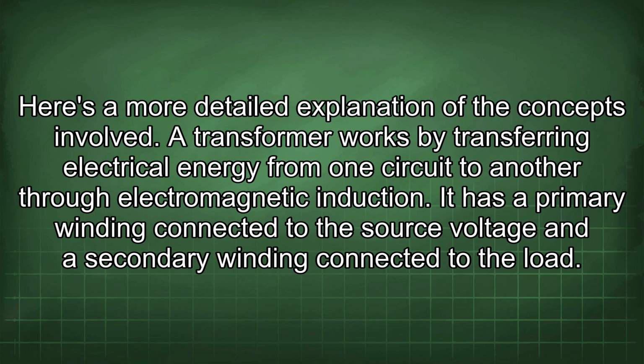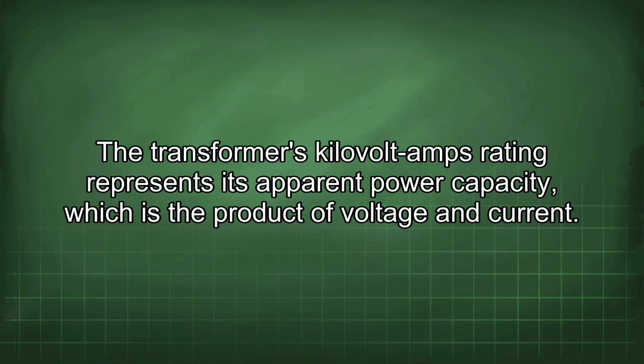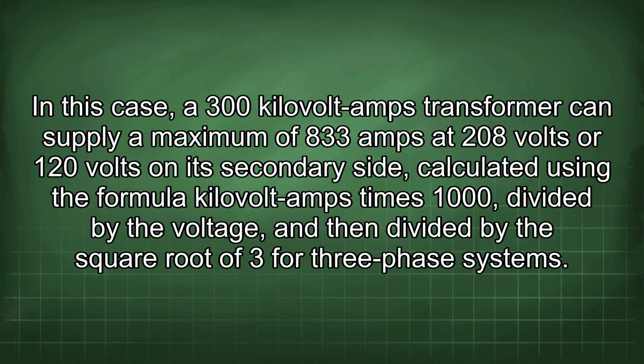Here's a more detailed explanation of the concepts involved. A transformer works by transferring electrical energy from one circuit to another through electromagnetic induction. It has a primary winding connected to the source voltage and a secondary winding connected to the load. The transformer's kilovolt-amps rating represents its apparent power capacity, which is the product of voltage and current. In this case, a 300 kVA transformer can supply a maximum of 833 amps at 208 volts or 120 volts on its secondary side, calculated using the formula kVA times 1000 divided by the voltage, and then divided by the square root of 3 for three-phase systems.